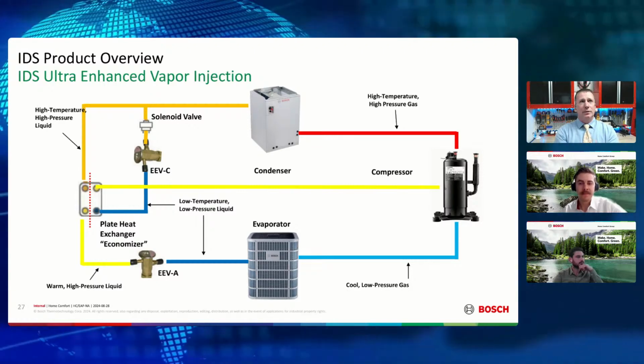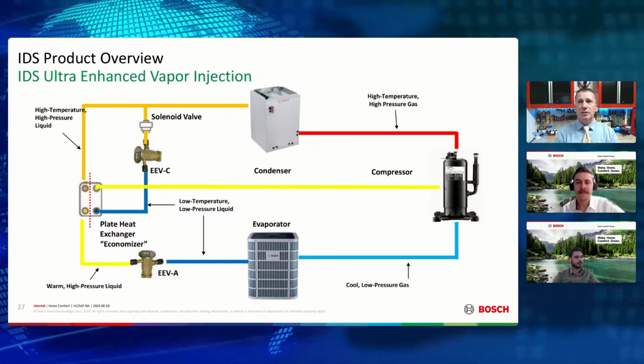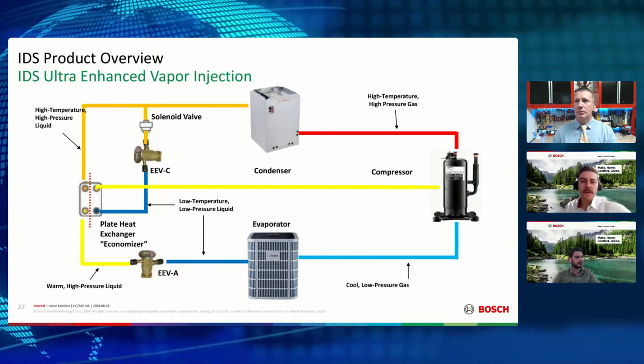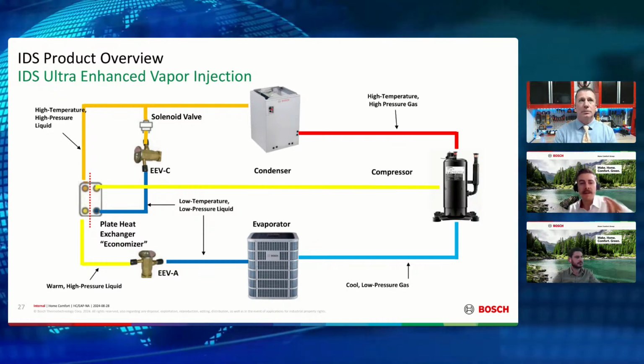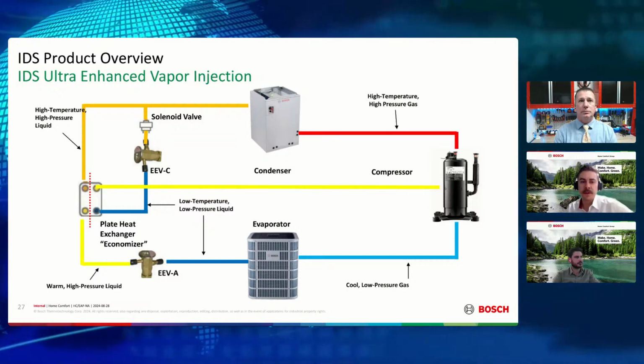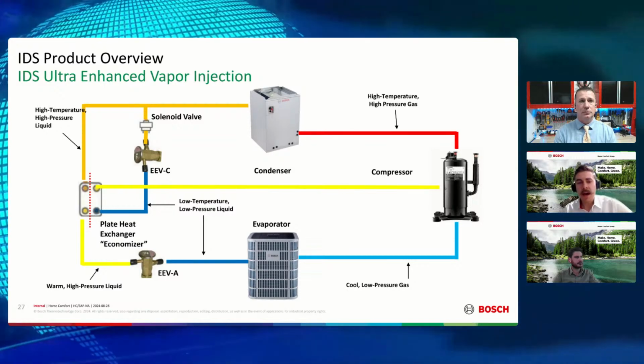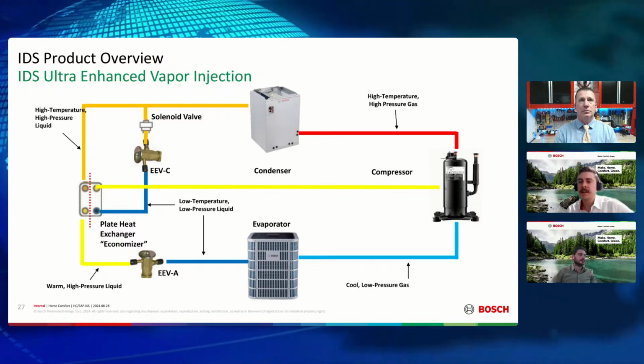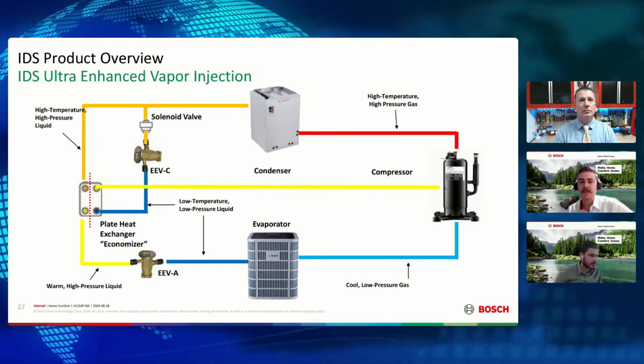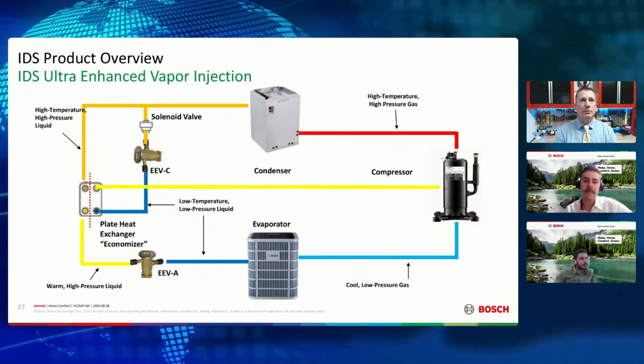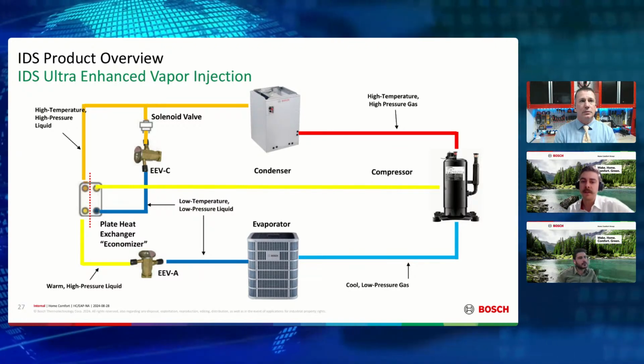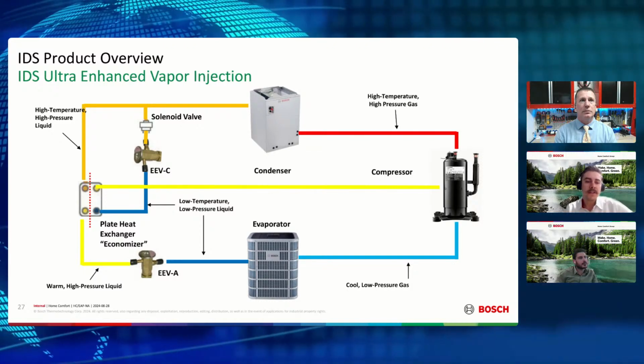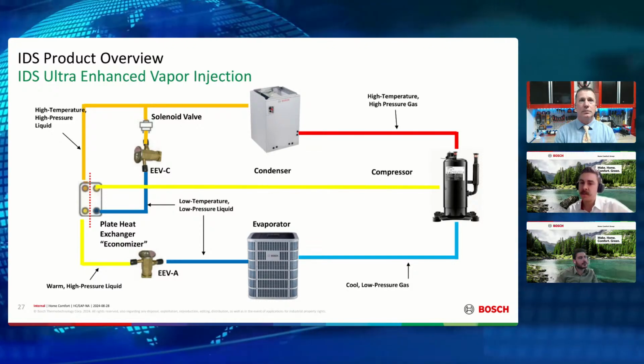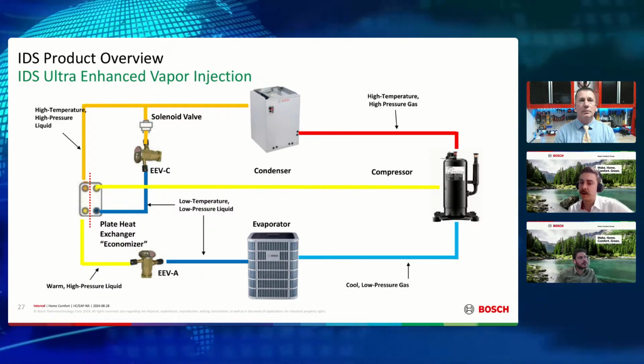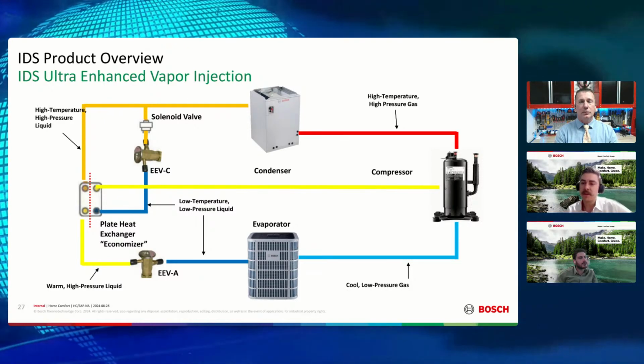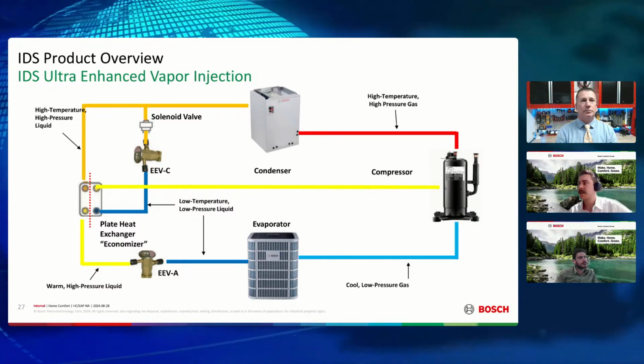So do you want to dive into what this enhanced vapor injection is doing on the system? What you can see here is basically a schematic of what we've got going on for the Ultra and the enhanced vapor injection. The outside of this loop is basically our traditional refrigerant system. We've got our compressor up top. Since we're in heating mode, our indoor coil is our condenser, then we go to the EEV-A, our expansion device, and then to the evaporator, the outdoor unit. That's how the refrigerant cycle works in this case.